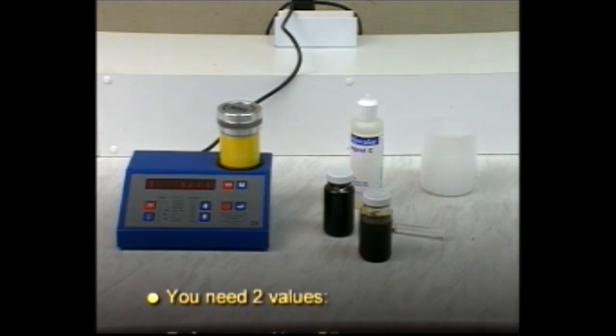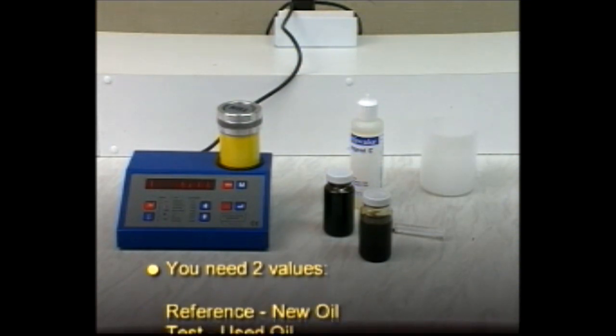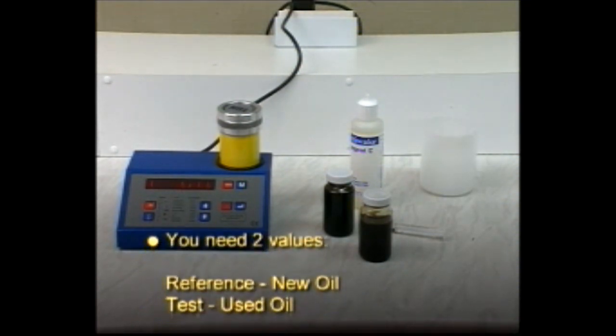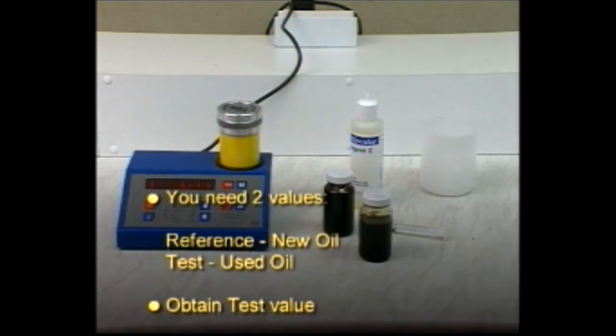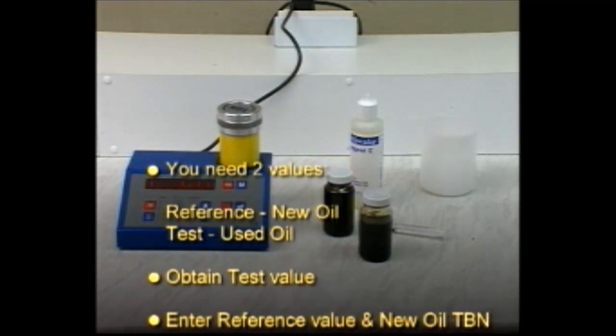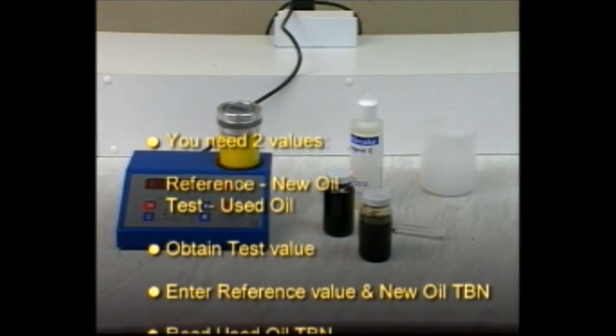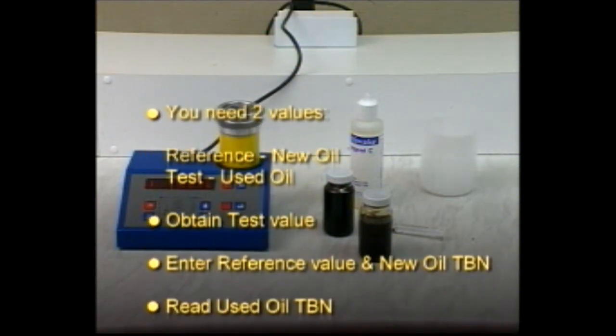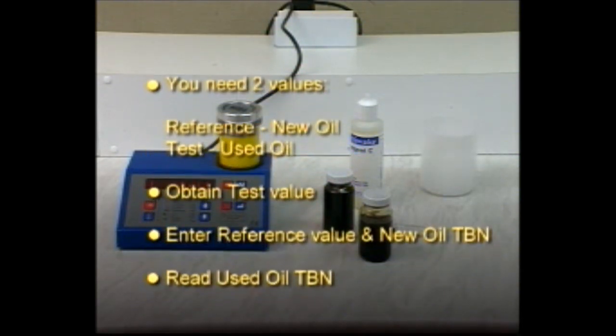To summarize, you need two values: the reference value from new oil and the test value from used oil. The used oil sample will provide the test value. Enter the reference value and new oil TBN. Read the used oil TBN.